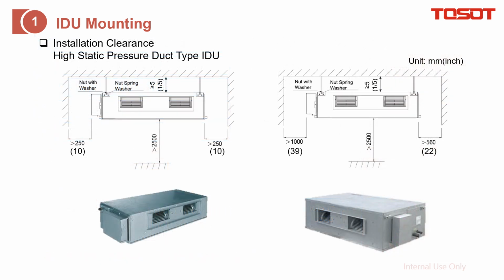And also during the indoor unit installation, you need to consider the clearance. This value depends on the type of indoor unit and also the capacity. So you can find that for the same high static pressure duct type, if the capacity is different, this requirement is also different. This is not only to ensure the capacity or performance, but also so that if something goes wrong with this indoor unit, you can do the maintenance. You need to consider the maintenance distance.